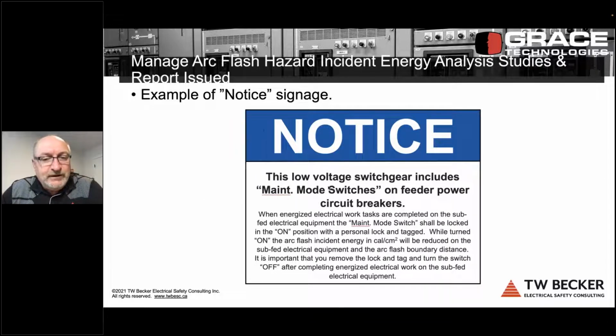I said, well, are other workers aware? Because it was new equipment, I said you should install this larger notice sign: this low voltage switchgear includes maintenance mode switches on feeder power circuit breakers, and provide some procedural instructions. This would be basically an 8.5 by 11 sign, so it stands off. You put it on the back, the front, and the sides of the switchgear as additional notice. The hierarchy of risk controls says warning signs and barricading. We need the worker to have more awareness that the outcome of the study was the installation of a maintenance mode switch to reduce incident energy on the electrical equipment that's being fed by the feeder power circuit breaker.